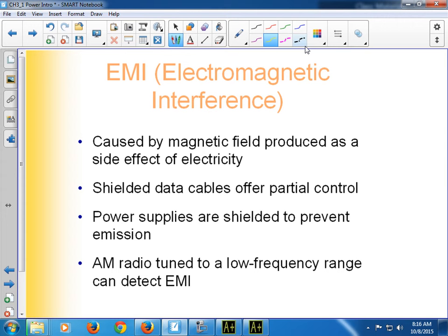And sometimes we'll have computers that act weird because the data cable is a poor unshielded data cable running on top of a high EMI device. We have had where the projection from an LCD projector is terrible, and all we had to do is move the cable, and all of a sudden it's fine. Because something up in the ceiling is interfering with the signal that's coming through the cable, and so all of a sudden you get a really fuzzy picture, and it wasn't the cable, it wasn't the projector, it was where the cable was running up in the ceiling. So it's just something to think about and something to know about, okay?